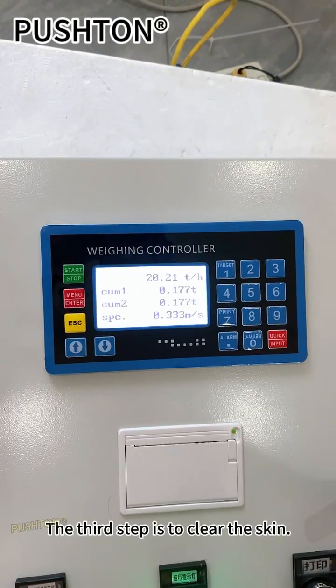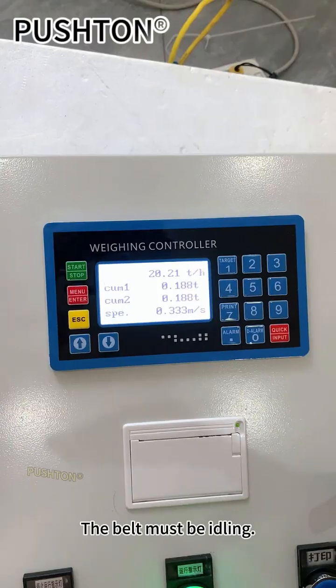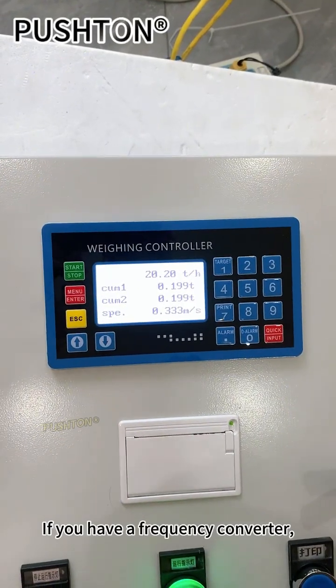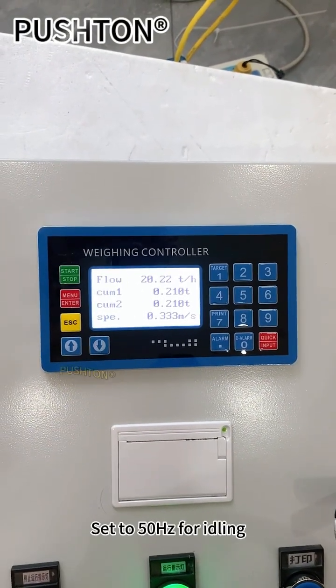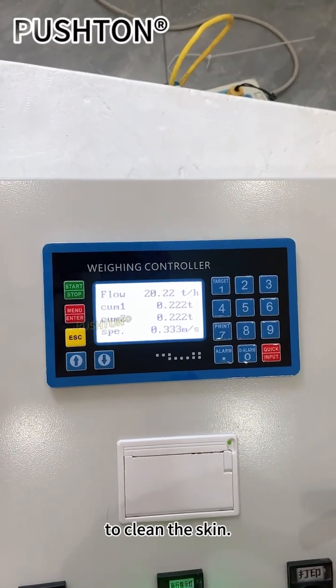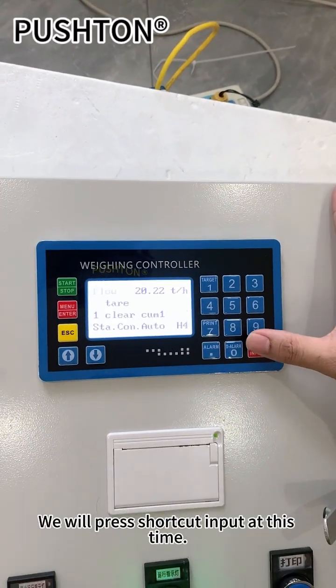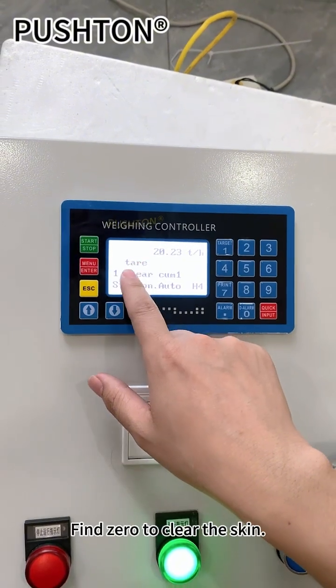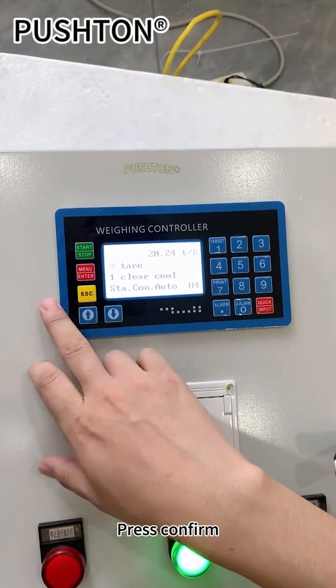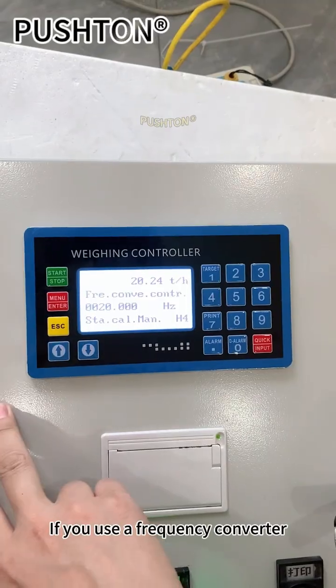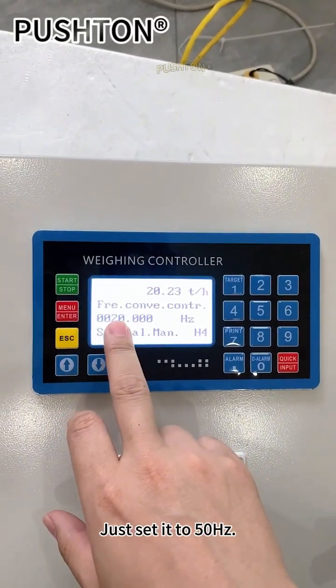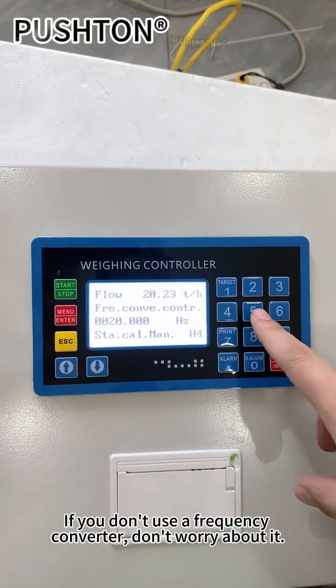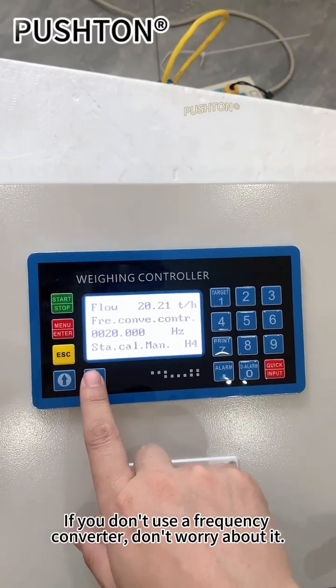The third step is to clear the tare. The belt must be idling. If you have a frequency converter, set it to 50 Hz for idling. To clear the tare, we press shortcut input at this time. Find 0, clear tare. Press confirm. If you use a frequency converter, just set it to 50 Hz. If you don't use a frequency converter, don't worry about it.